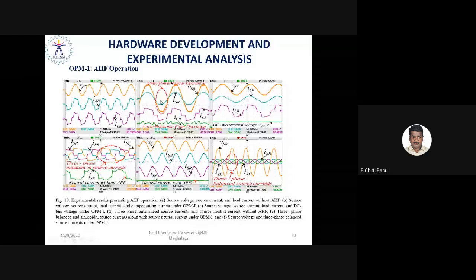By proposing the active harmonic filtering operation with the inverter control, it is trying to shape your grid current waveform sinusoidal, and again it is in phase with voltage, so that the power factor becomes unity, and moreover the power quality problem can also be mitigated, right? And you can see the compensating current by the inverter, and moreover the three-phase load current profile is available.